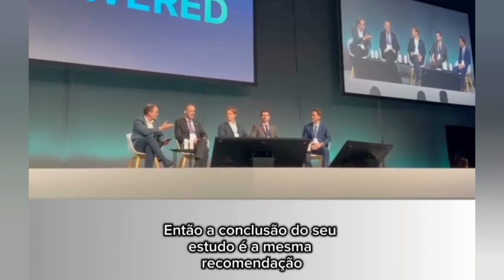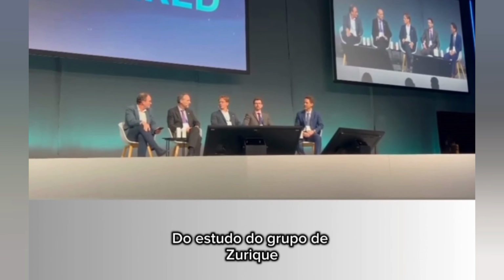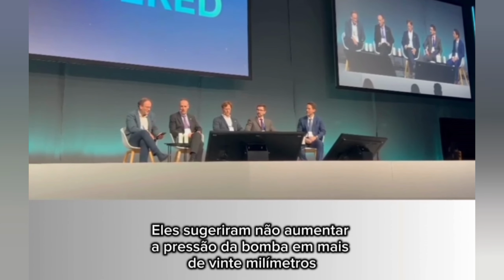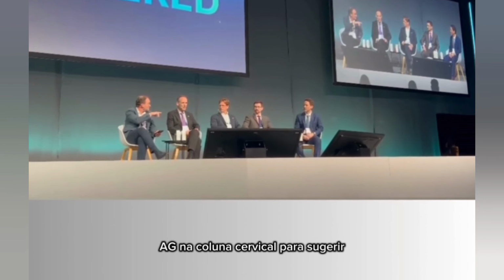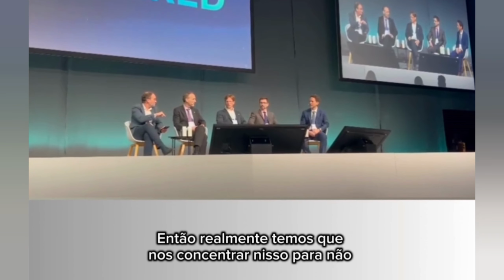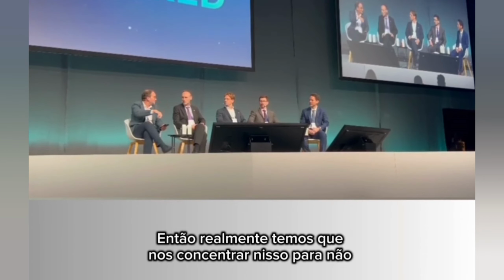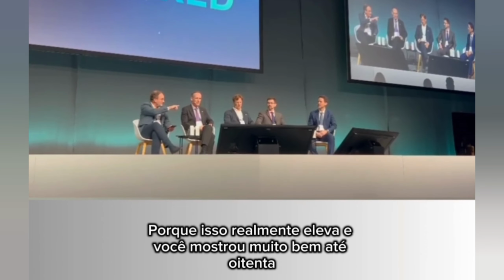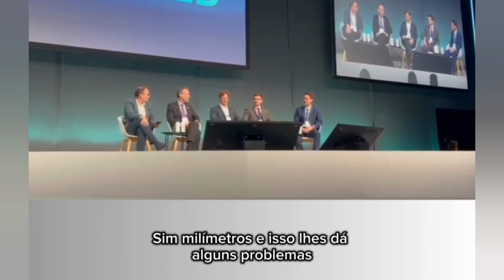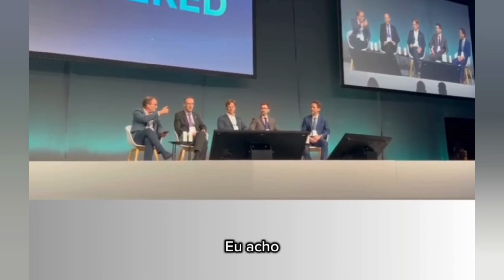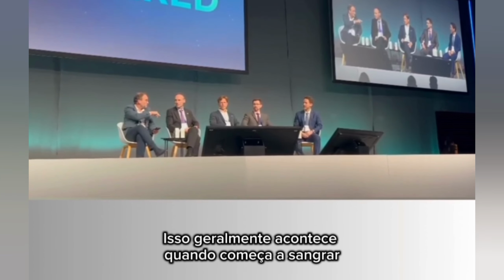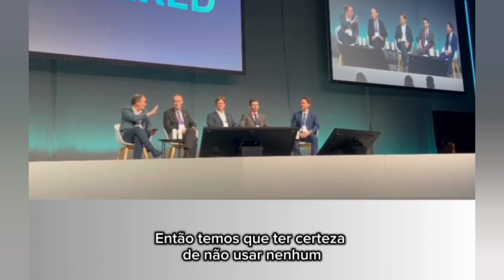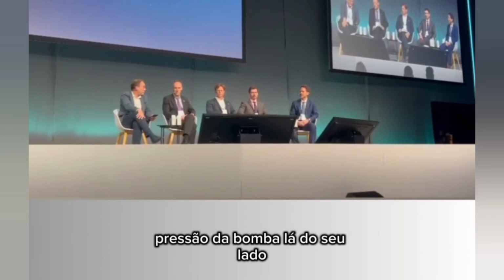So the conclusion of your study is the same as the recommendation from the Zurich group, Farshad. They suggested not raising the pump pressure over 20 millimeters of mercury in cervical spine procedures. So we really have to focus on not closing the water flow exits. Because that really rises, and you showed it really nicely, up to 80 millimeters, and that gives problems. I think this usually happens when it starts to bleed, so we have to make sure not to use any higher pump pressures there. Right? Yes, good.